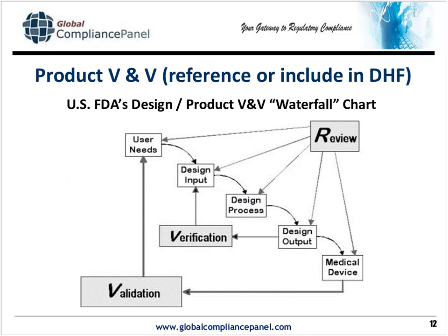Now here's the slide I was referring to. The FDA, I believe, borrowed this from Canada, but nevertheless, it's an excellent illustration of the principle regarding product verification and product validation. Those of you that look at those terms under ISO and GMPs know that they have different meanings under different schemes, like process validation means a different thing. And also the subtle wording differences between those two definitions can be somewhat confusing. But this slide, at least as far as what we're talking about, product validation is very vivid, if you will.